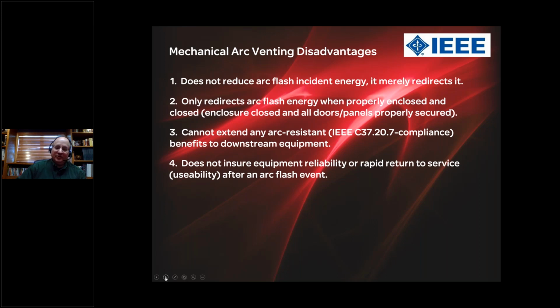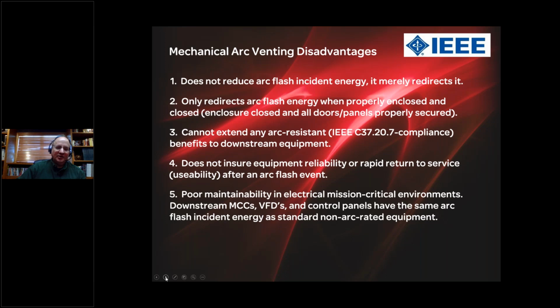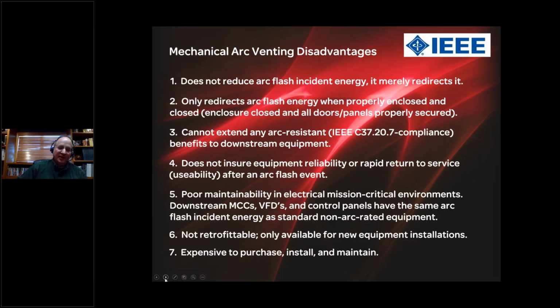The equipment itself, if you're in a critical power environment, is going to ensure long downtime, even if it can be somehow repaired. It has poor maintainability in electrical mission critical environments. Downstream MCCs and variable frequency drives and control panels now have the same arc flash incident energy as standard non-arc rated equipment, unless you buy a separate arc resistant mechanically vented MCC or drive. It's not retrofittable. Mechanical arc venting is only available in new equipment installations. And the seventh sin, it is expensive to purchase, install, and maintain.